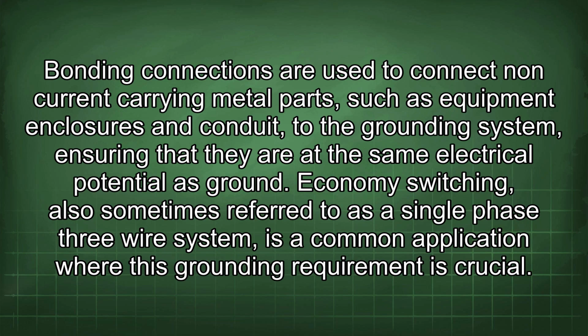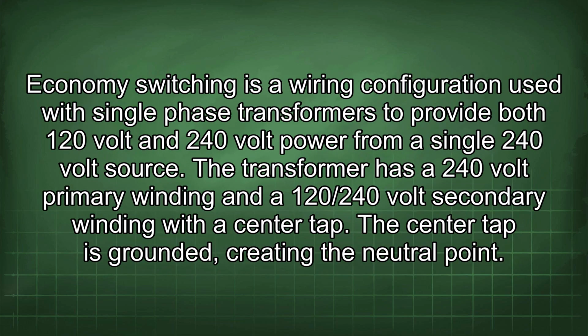Economy switching, also sometimes referred to as a single-phase 3-wire system, is a common application where this grounding requirement is crucial. Economy switching is a wiring configuration used with single-phase transformers to provide both 120 volt and 240 volt power from a single 240 volt source. The transformer has a 240 volt primary winding and a 120/240 volt secondary winding with a center tap. The center tap is grounded, creating the neutral point.